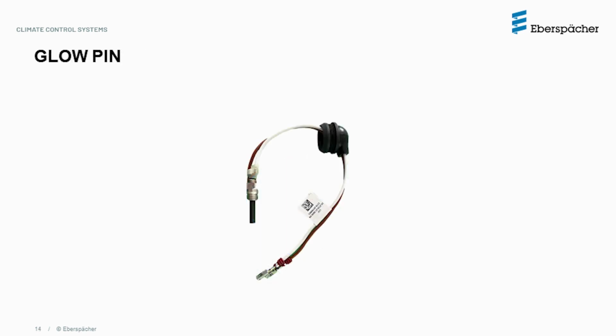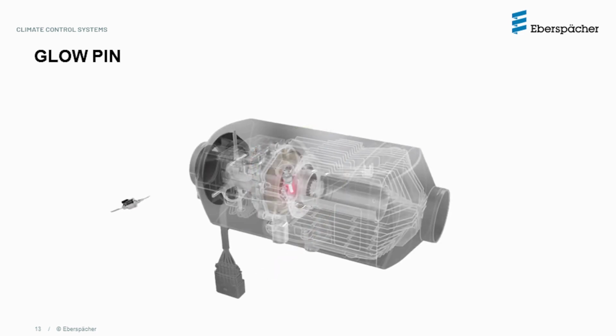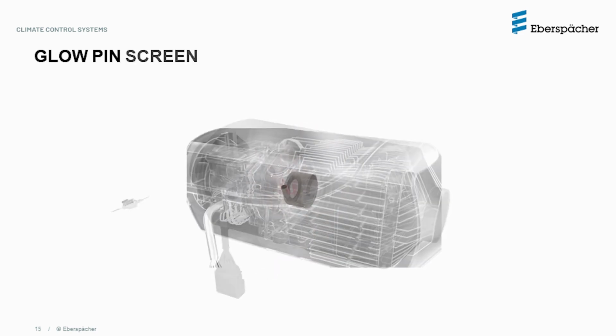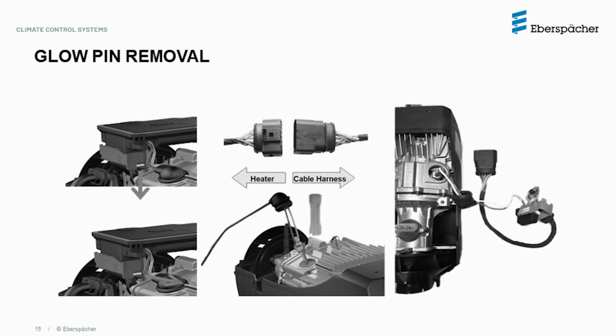The basic design of the Airtronic 2 glow pin is the same as before, except now it has terminals instead of an electrical connector. The glow pin ignites the fuel-air mixture. The Airtronic 2 glow pin screen is exactly the same part as used in the previous generation heater. Removing and replacing the glow pin screen is part of the annual recommended maintenance. The glow pin will have to be first removed to gain access to the glow pin screen. The glow pin can be removed without unpinning the terminals. To do this, disconnect the internal harness from the ECU and also disconnect it from the main heater harness. Loosen the glow pin and then rotate the internal harness with the glow pin, making sure that the glow pin cables are not being twisted.